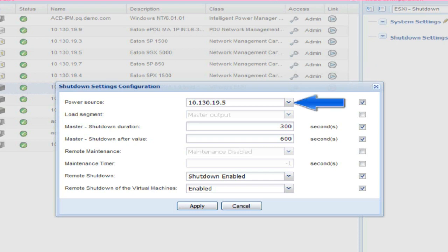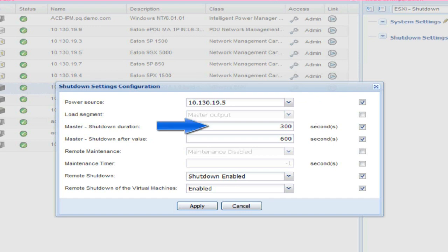Power Source: select the IP address of the UPS which powers your host. Load Segment: designate the output receptacle which the host node is connected to on the UPS. Typically, this will be the master segment. Master Shutdown Duration: enter an amount of time in seconds which will dictate the length of time the host will have to complete its entire shutdown. The virtual machines will shut down first and then the host. Once the designated time expires, the UPS load segment will de-energize.